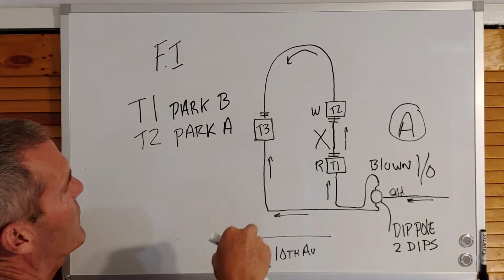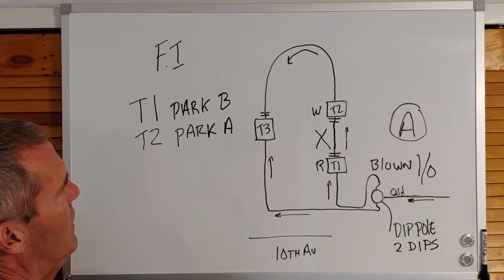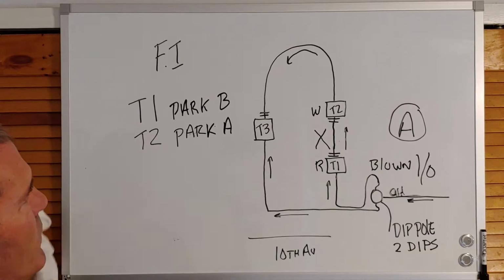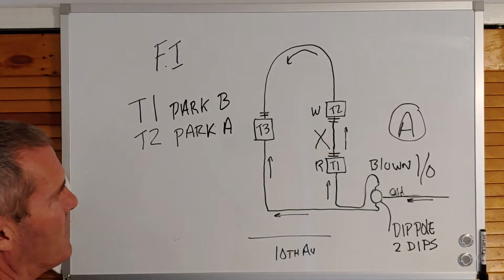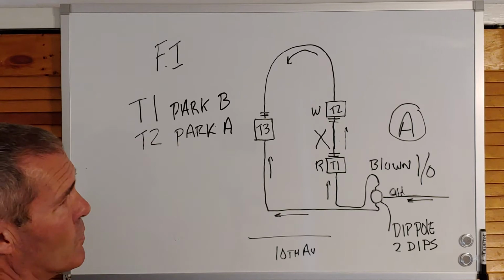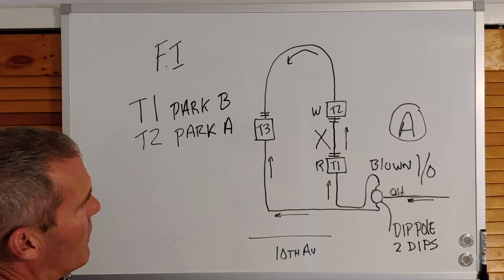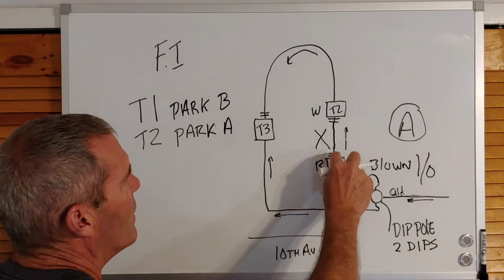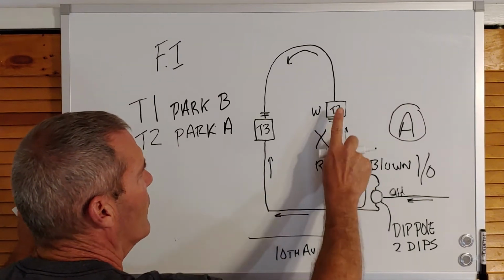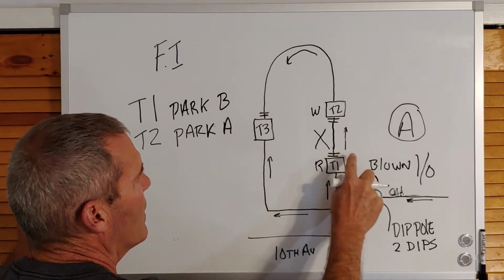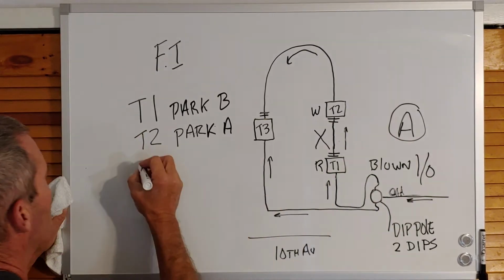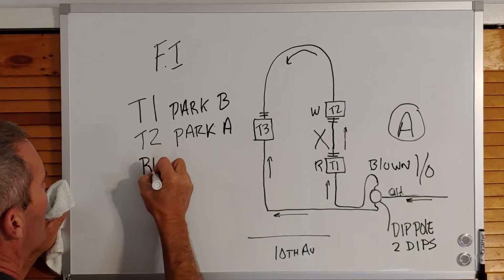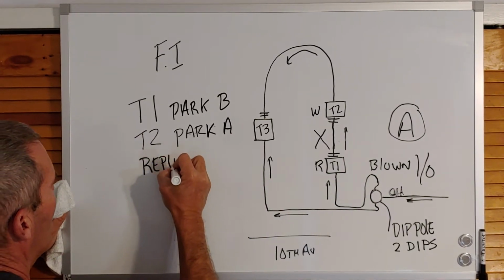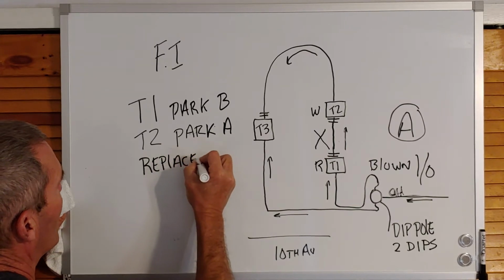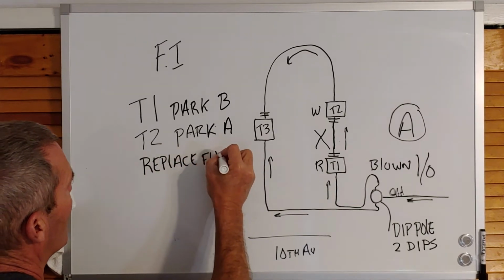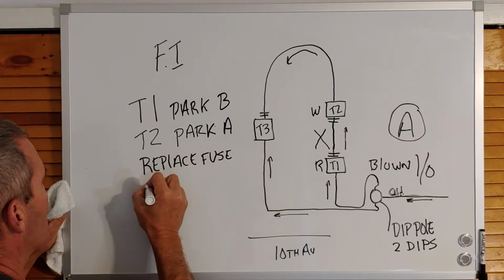All right, that's still the faulted span. We're just going to leave that in that situation. So with this span of cable isolated, I now need to restore power. How will I do that? Now that power can no longer travel along this line, since I've dead ended it, we're going to replace the fuse and close it.